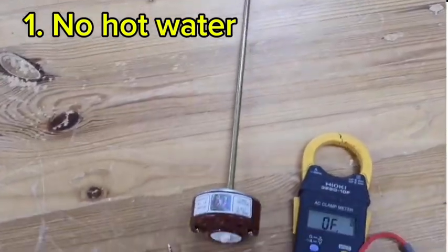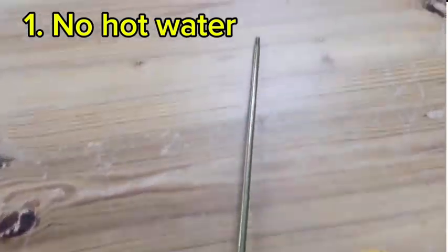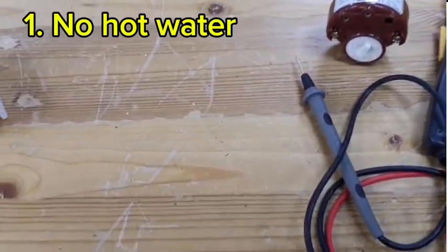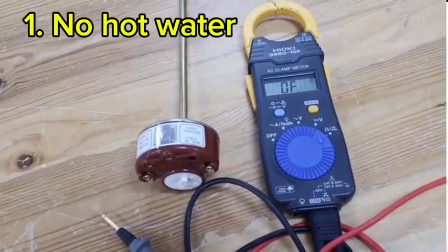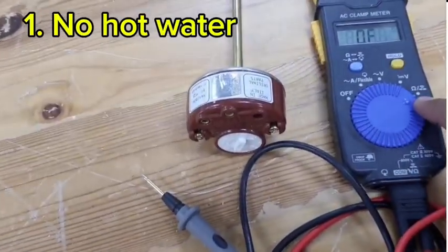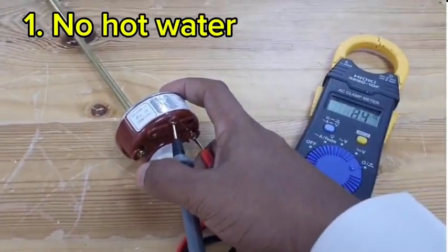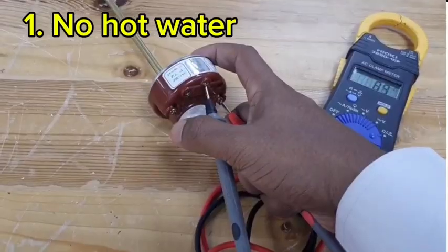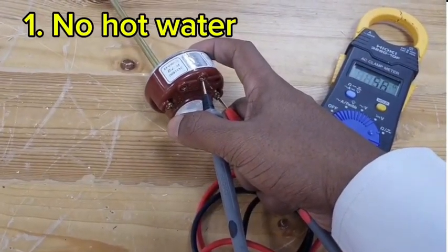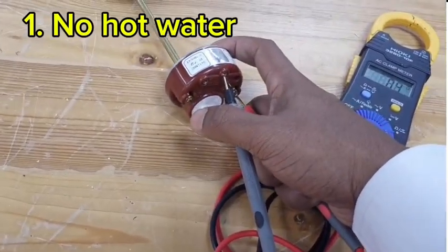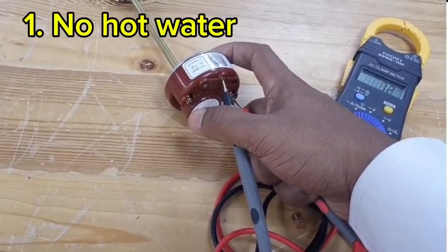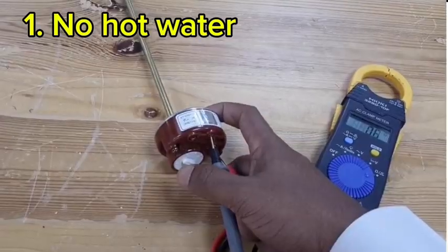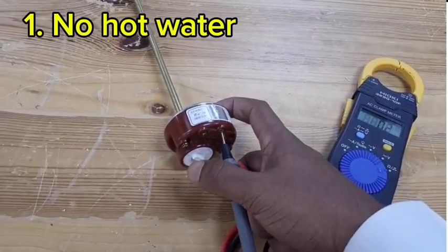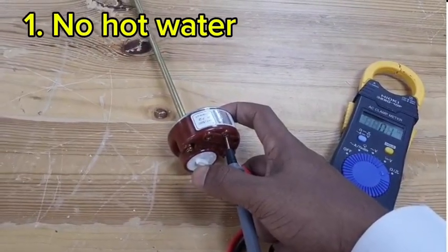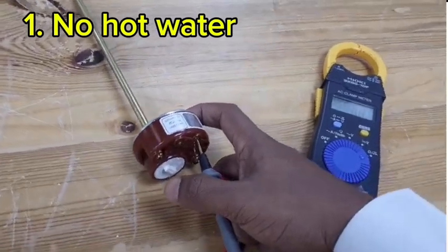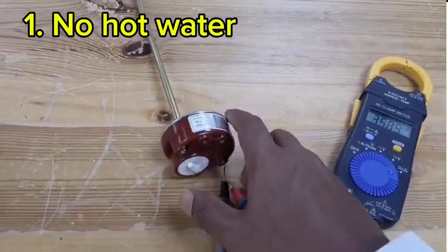So this is the thermostat. This is the thermostat I have taken from the water heater. Now I am going to check the thermostat. For checking the thermostat, I have put my multimeter on continuity. See, when I check the continuity, you can see and you can hear a sound. This is the continuity of the thermostat. If there is no continuity, it is open. That is how you can check your thermostat. There are 4 terminals: L to 1 and N to 2. So there is continuity, which means the heating element or thermostat is in good condition.